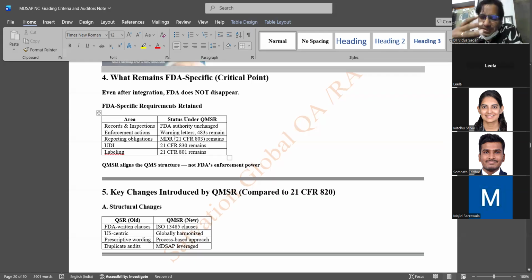Medical device reporting is basically on the adverse events and regulatory advisory notices. This is medical device reporting. It comes in 21 CFR 803. This remains separate. So you know now you have 820, that is basically the QMS or QSR of USFDA that will come in. But this they may not come in, but you need to align them separately. Okay, 803 on medical device reporting, adverse events, advisory notices. 830 on UDI, basically unique device identifier. Okay, on 830, labeling is 801.